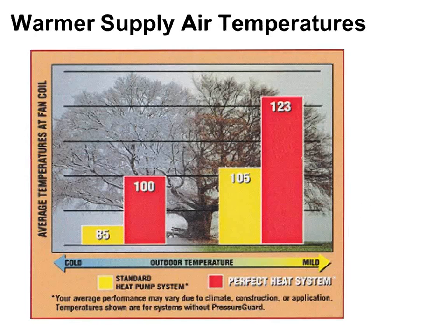Normally, what I want to do is keep the supply temperatures above 100 degrees if I can. Then people won't object, because it won't be blowing cool air across their skin. Traditional heat pumps, when it's mild outside, meaning like 50, 60 degrees out, I'm able to get above 100 degrees. In this example, I got a 105 degree discharge with a specific single stage heat pump. And then my two stage or variable speed ones, I can have an even higher discharge and still maintain control.